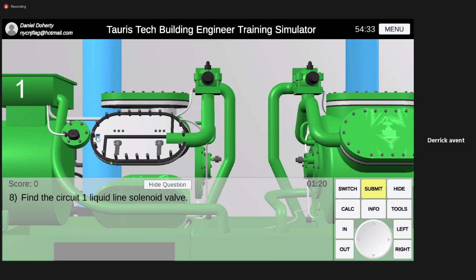Okay, so the vapor comes up on the low side here, and it gets sucked into the suction valves. On the downstroke, it's still low pressure. Then on the upstroke, these valves close, and the vapor gets compressed into high pressure. And then when it comes out of the discharge valve, now you're on the high side of the machine, okay? So now you have high pressure, high temperature, superheated vapor.